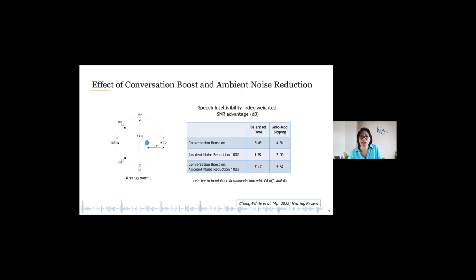So looking at the effect of these new features, there's conversation boost and ambient noise reduction. We calculated the difference in the signal-to-noise ratio between using headphone accommodations with these features turned on, compared to when they're turned off. And then to relate that SNR advantage to speech intelligibility, we applied band importance weights that were based on the speech intelligibility index.